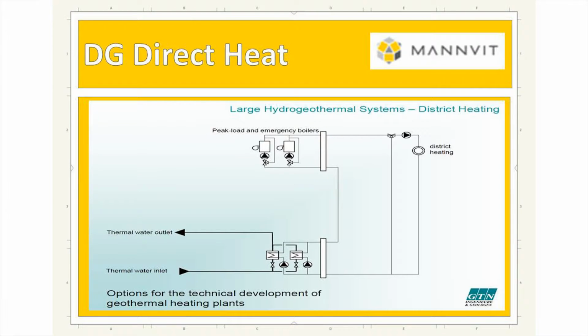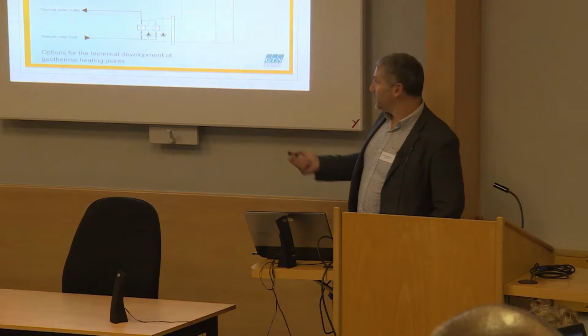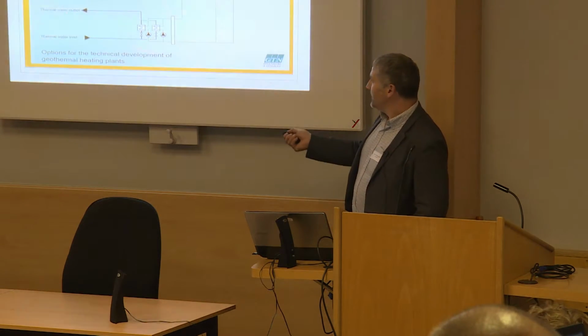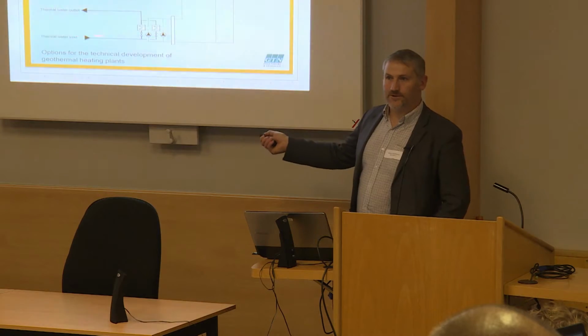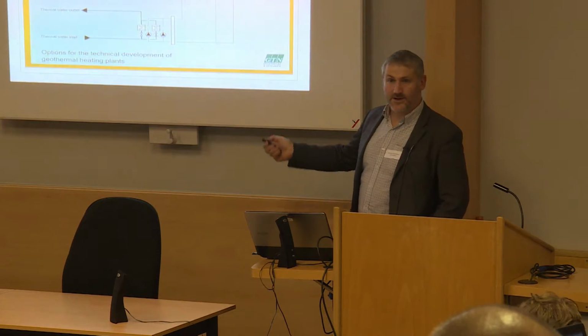This is deep geothermal direct heat - just a very simple kind of model that we have. GTN are one of the companies we own in Germany, and they've done some pretty decent systems over there. Basically, you have a thermal water inlet that comes in through the heat exchanger and then goes back out of the system. Then we feed into a district heating system, with a peak load and emergency boilers for when the system needs amending or the pumps need to be changed. So, about as simple as it gets - this is no different, it's a heat source. Yes, it is technical to work out and manage, but it's just a heat source.